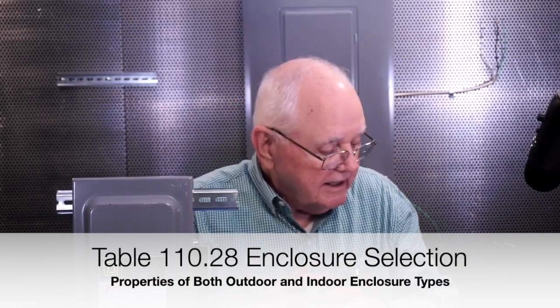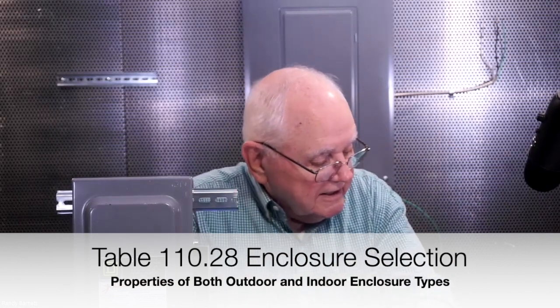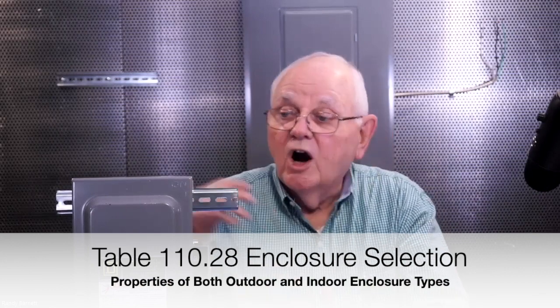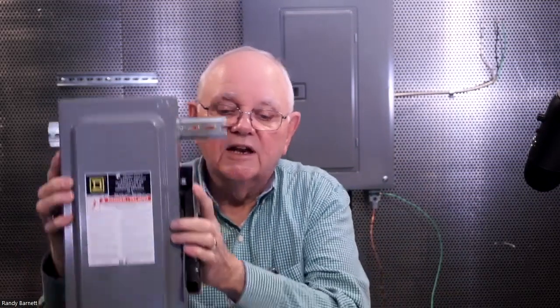So if we look at the indoor, we find that a type 1, they all prevent incidental contact, right? These enclosures, so that we don't accidentally touch something we shouldn't. Other than that, it's good for falling dirt. And that's about it for a type 1. Also, I'll mention, let's talk about this as a general rule for all of your disconnecting means, whether it's this, a molded case circuit breaker, whatever it is.